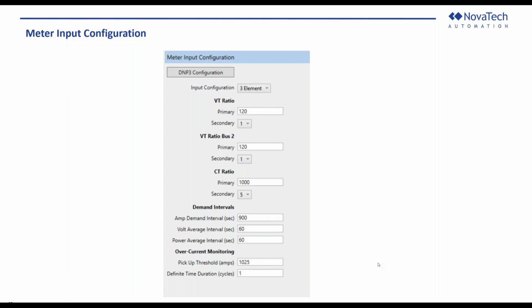User can also set up the overcurrent monitoring. I've set it up to 1,025 amps, so anytime it exceeds that threshold, overcurrent will be picked up for a definite time duration. It's 1 cycle. It can be changed to up to 60 cycles.